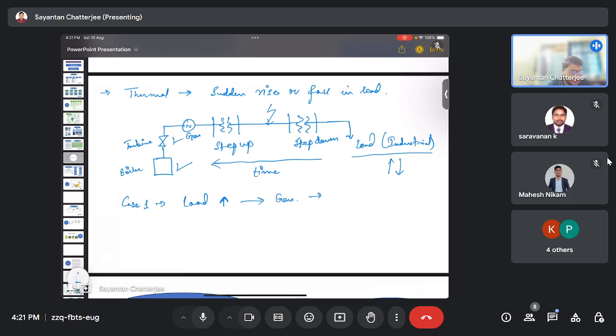So we would face a frequency shift. Frequency deviation is observed. This frequency deviation we will face, and the direction of this deviation, whether rise or fall, is based on the difference between load and generation. If load is high and generation is low, then frequency would drop. If load is low and generation is high, frequency would rise.